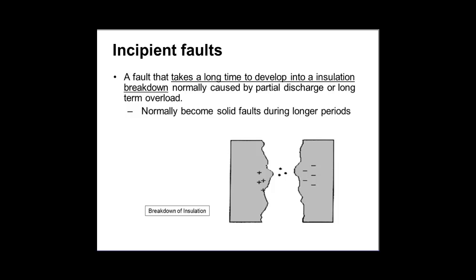What I'm saying is that if you ignore this overload, saying, oh man, this is not a fault, it's not a puncture, for example, to a cable, it's just an overload. It was just a little bit of overheat. Why are you making a big story of something? Well, did anything happen? No, I was there 5 minutes, 10 minutes, nothing happened. Yes, you're right. Nothing happened. But all I'm saying is that you were never supposed to use this transformer like that. That was the rating given to you. You exceeded that, not just one time, 2 times, 10 times, 20 times.